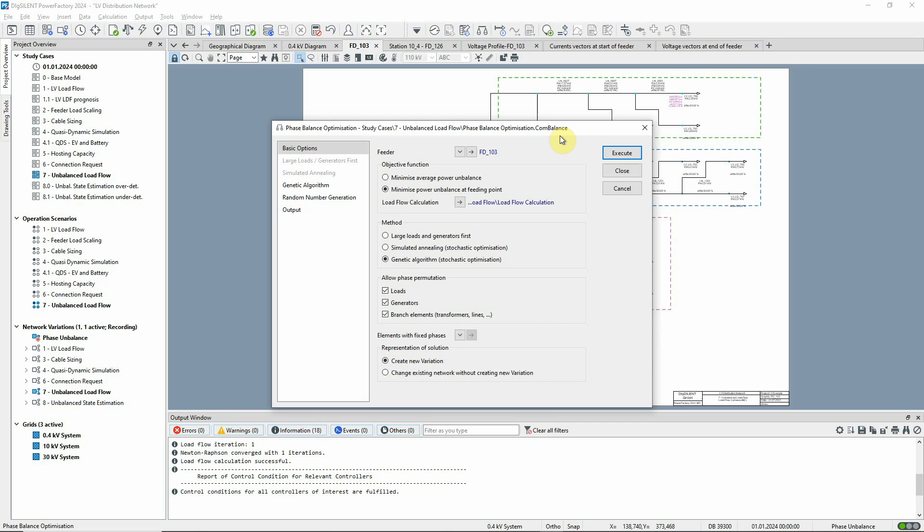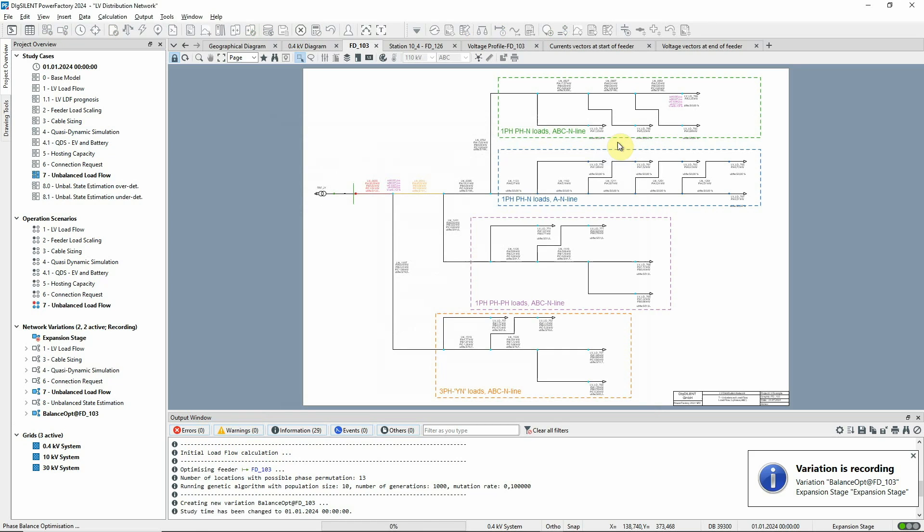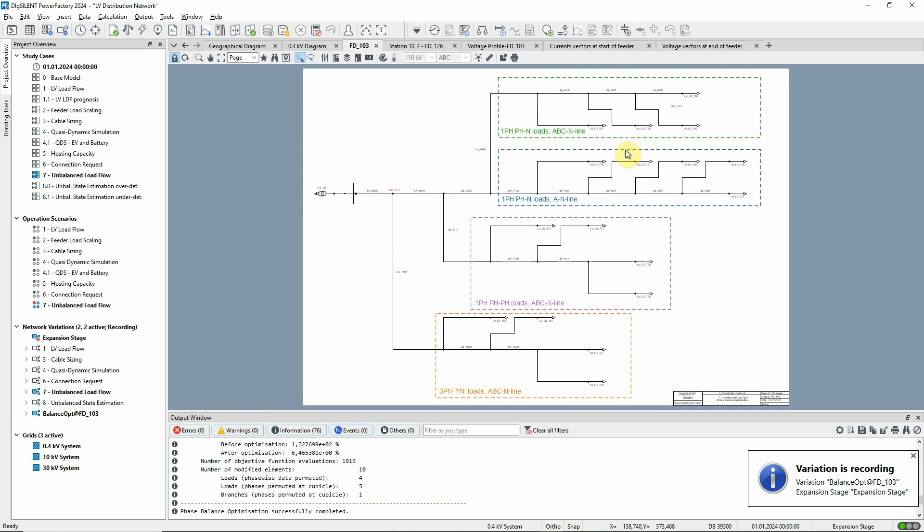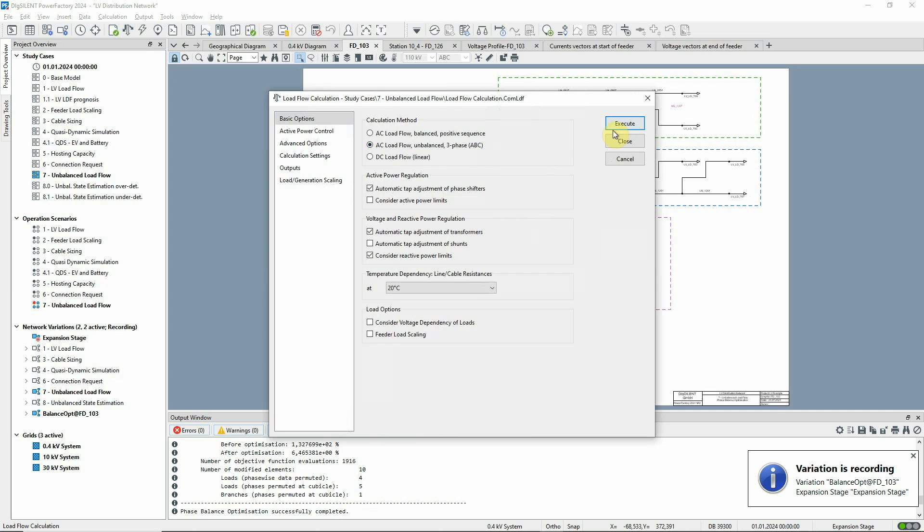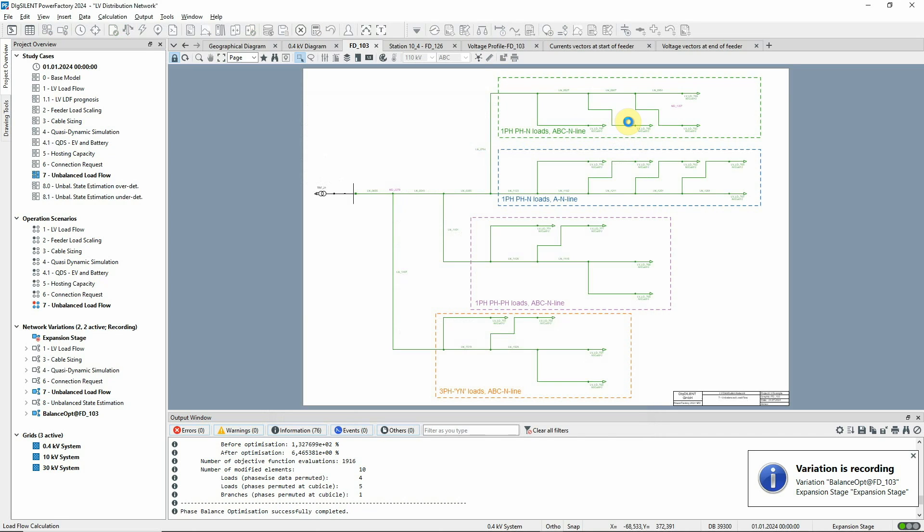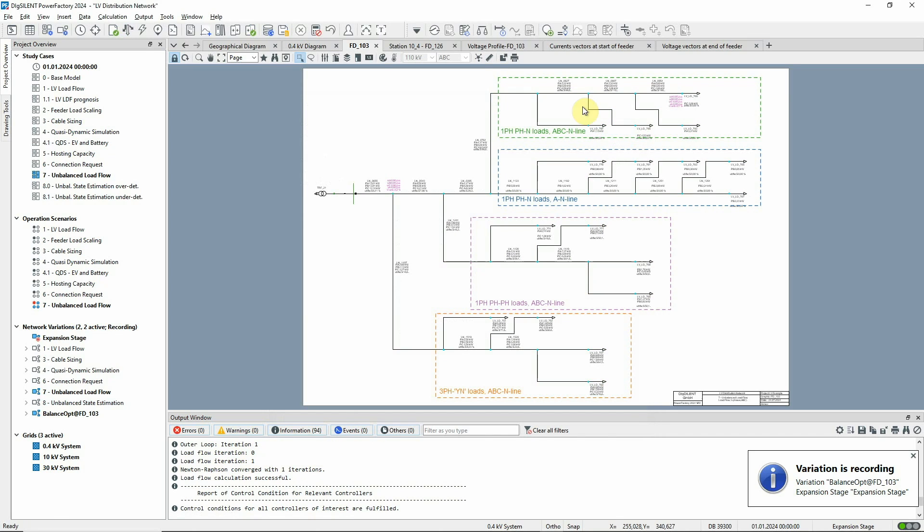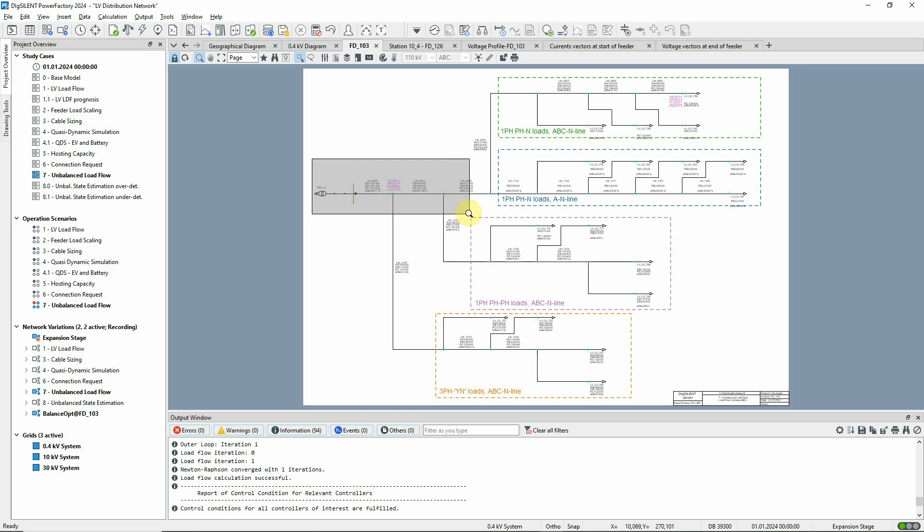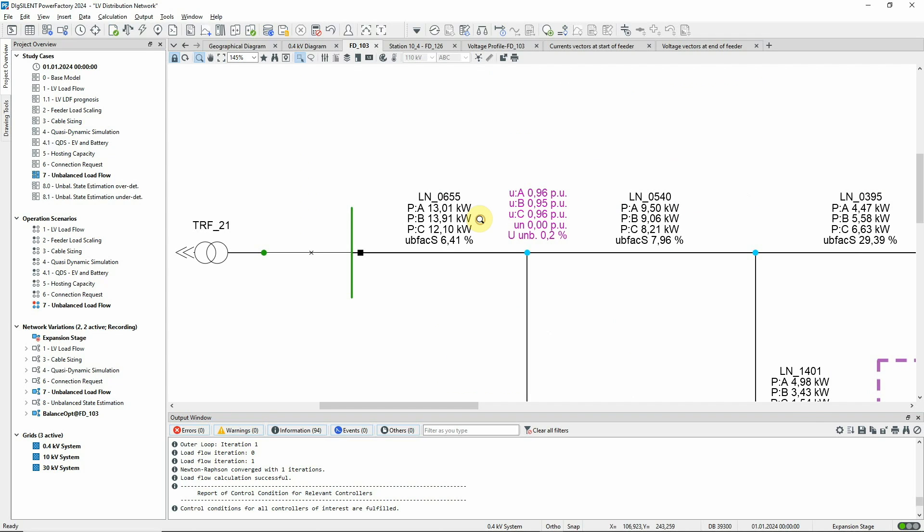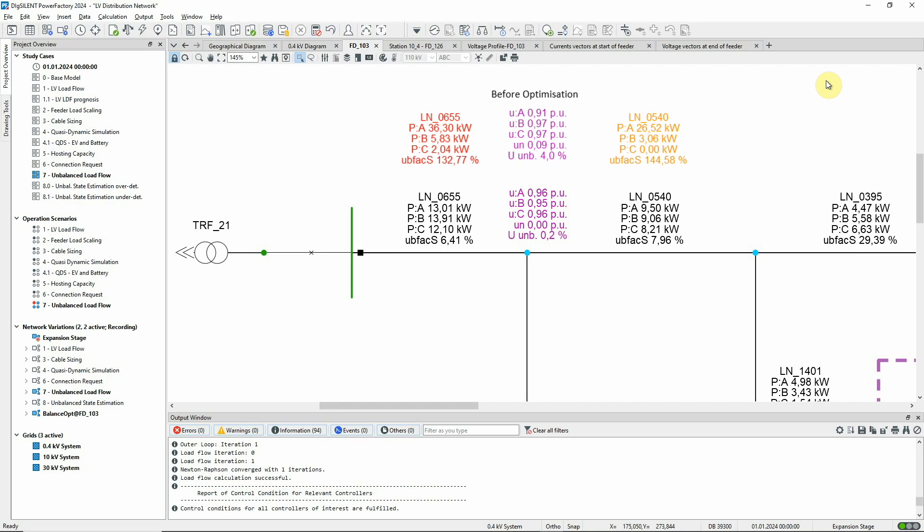The optimisation command is executed. You can see that a new variation has been created and is activated. With the optimisation complete, let's now run another load flow. We can see that the results show an improvement. The imbalance factors of both the voltage and power have been reduced.